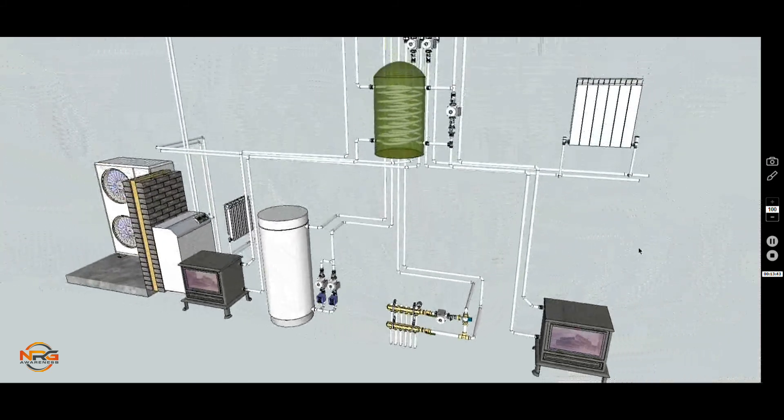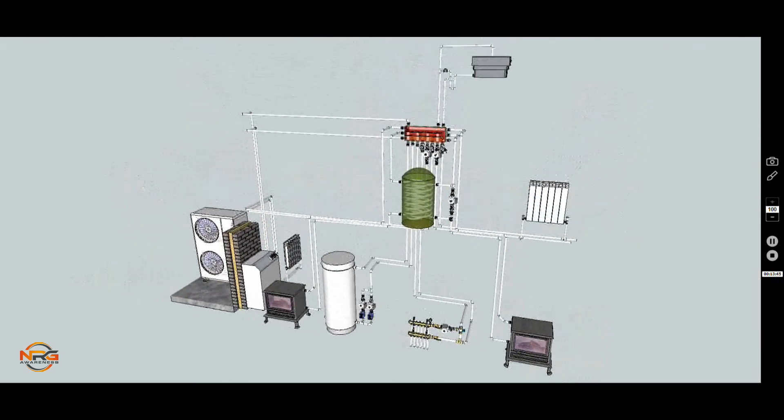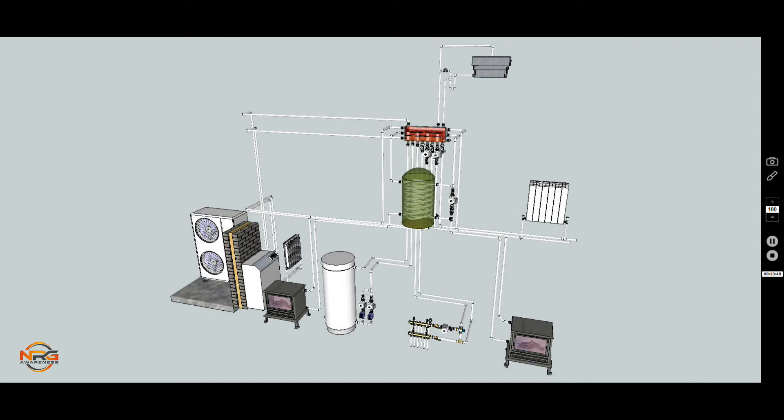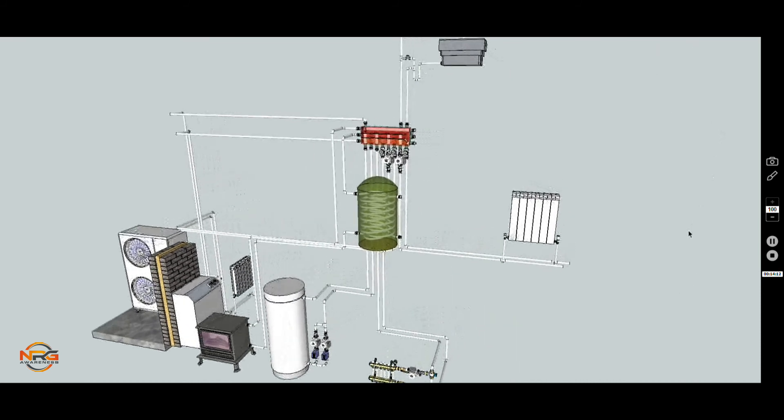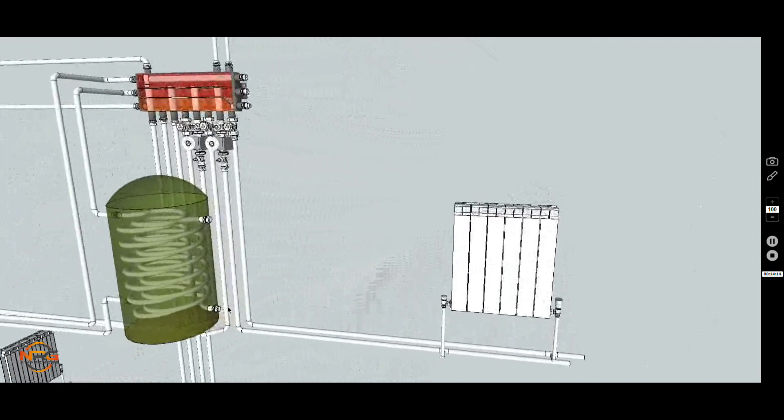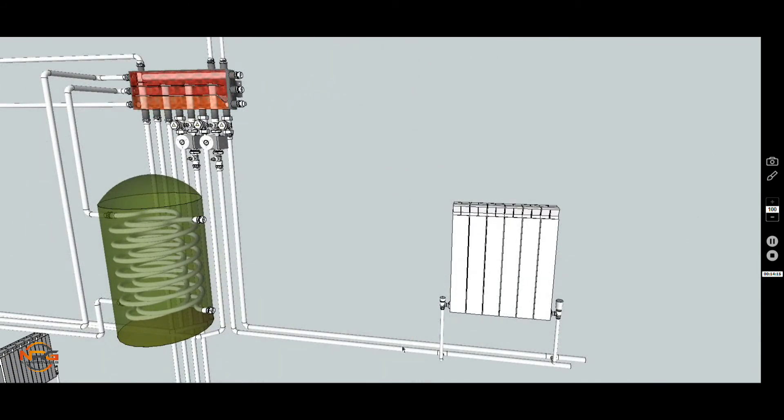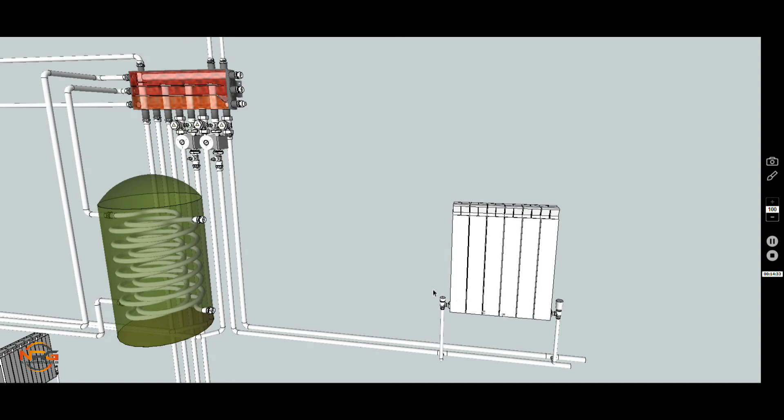If we want to put in an upstairs radiator circuit, we could do it by simply putting a pump that would pump down and across to the radiator circuit and carry on to whatever other radiators we have or heat output. The return would come back and be brought up and put back into the non-return valve into the lowest chamber, again making the coldest water in the system available for whatever heating equipment is best to use. You'll see pump and non-return valve. The reason for the non-return valve is if the pump isn't working, you don't want to take a chance that any heat might start to drift backwards down through the system. The non-return valve is simply a precaution to make sure there's no inadvertent heat leak out into a zone that isn't required at that given time. You would have non-return valves on any zone circuit.